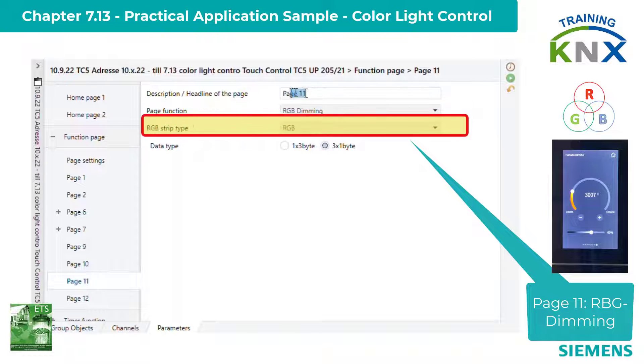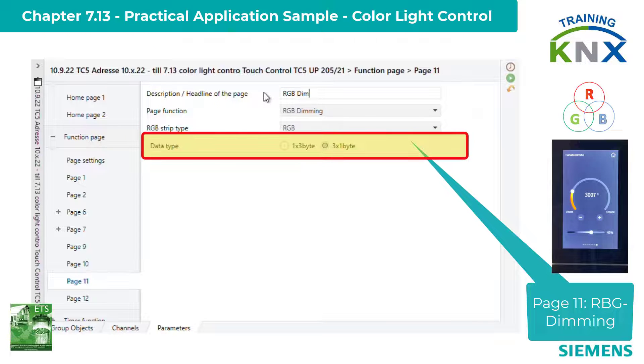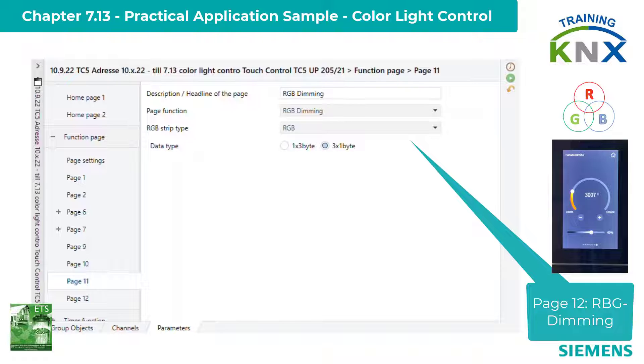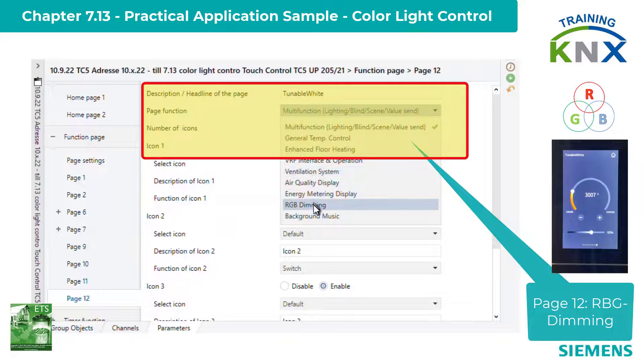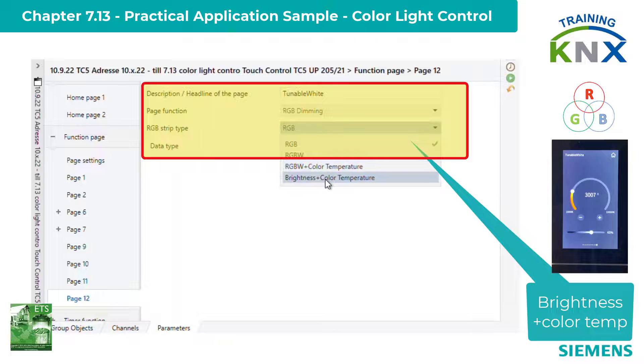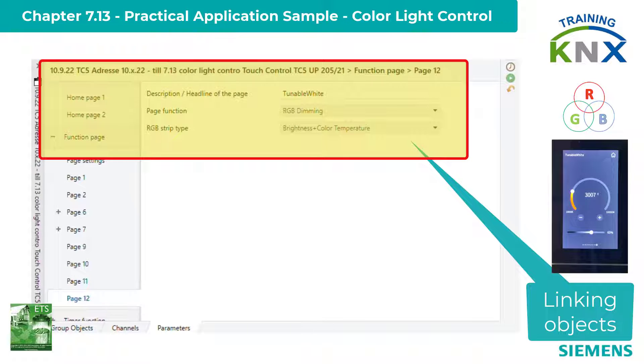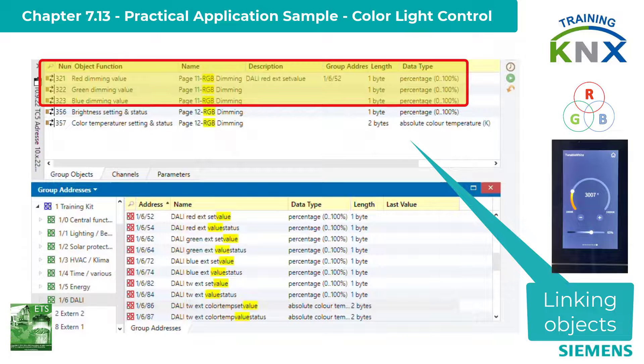Then the strip type RGB and finally data type three times one-byte. On page 12, it gets even simpler. The RGB strip type is set to brightness plus color temperature. We edit the objects. On page 11, the three one-byte objects of the three colors are linked.